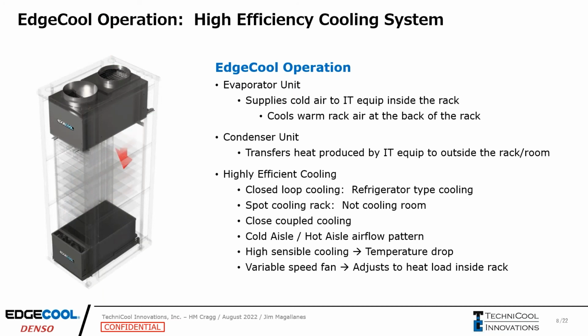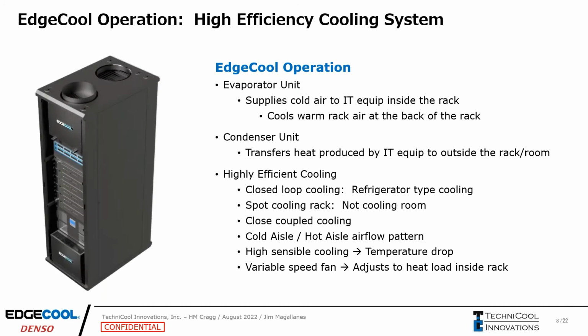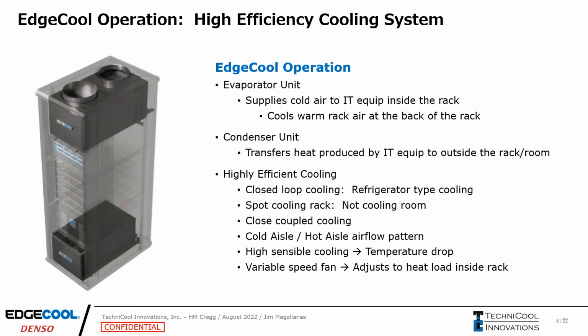And so that's key. We have an inherent cold aisle, hot aisle airflow pattern going on within the rack. So that's a best practice within data centers, larger data centers, where they have rows and rows of cabinets, and they have cabinets facing each other. So there's a cold aisle where all the fronts are facing, and then a hot aisle where all the backs are facing. We're doing the same thing here within our rack. And so we're bringing that efficiency that's been going on in the bigger data centers down to the rack level here.